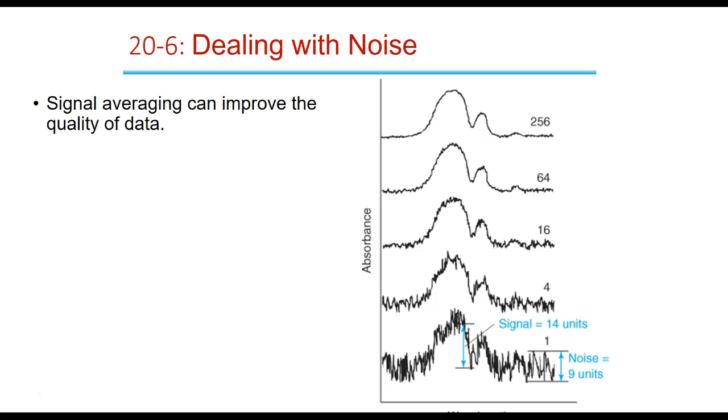And look at how good it looks. Good meaning clearly there's something: 1, 2, 3. Now the third one, I'd still like to see a little bit more definition, some resolution improvement, but we definitely feel good now about those two peaks at 256. I mean, look at the increase in signal.